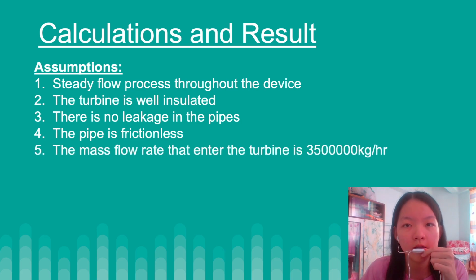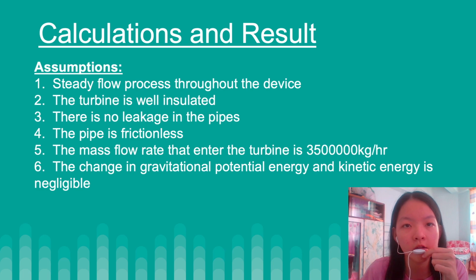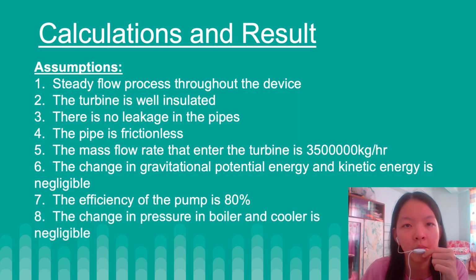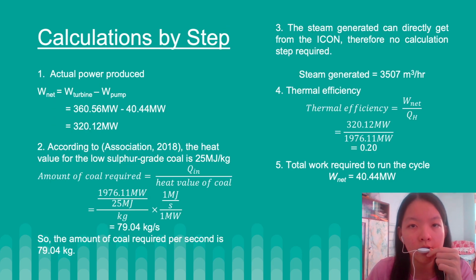The fifth assumption is the mass flow rate that enters the turbine is 3,500,000 kg per hour, which was determined by using the ICON simulation software in order to get the design power, which is 280 megawatts. The sixth assumption is the change in gravitational potential energy and kinetic energy is negligible. The seventh assumption is the efficiency of the pump is 80% in order to reduce the energy loss to the surrounding. The eighth assumption is the change in pressure in boiler and cooler is negligible in order to make the calculation easier. The calculation is made based on the result from ICON simulation software.